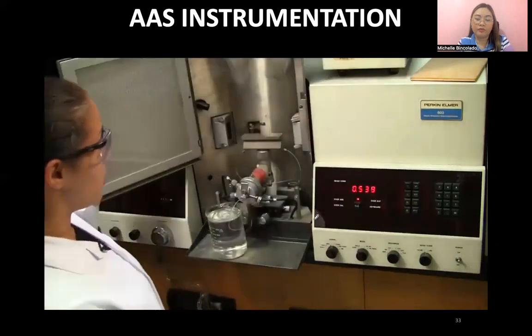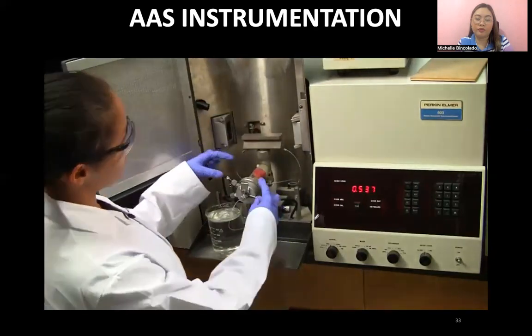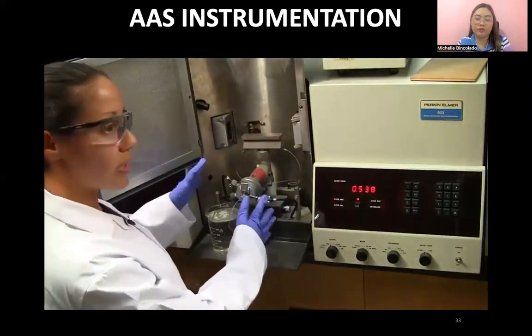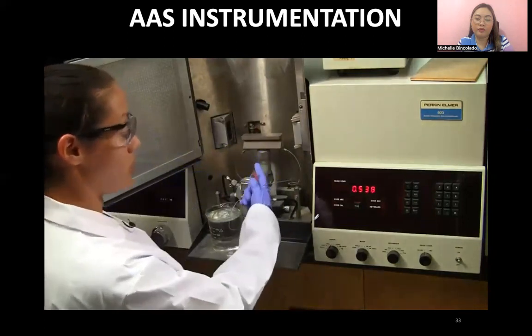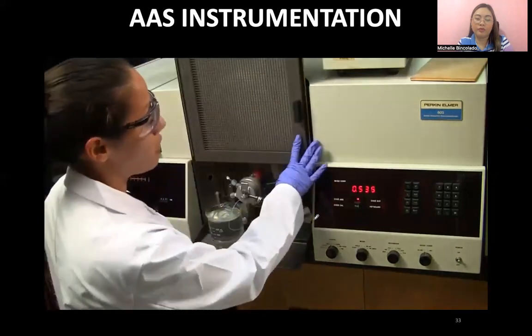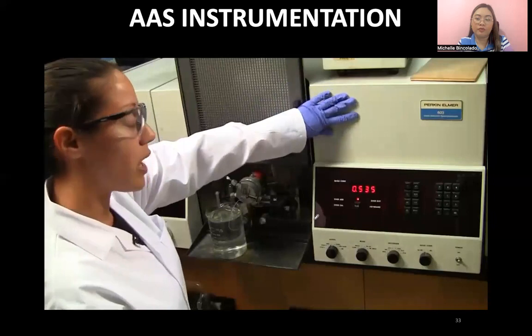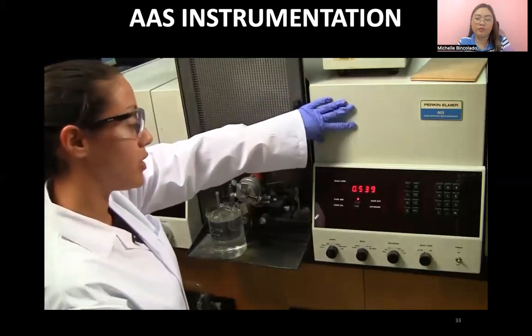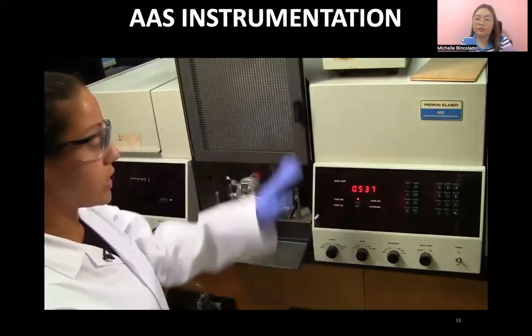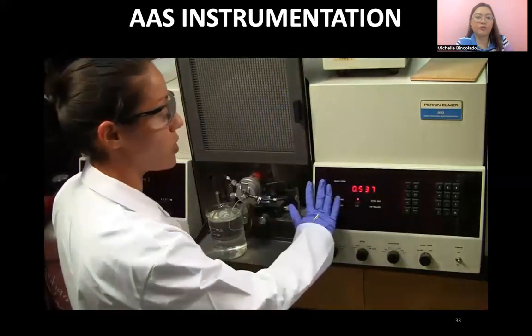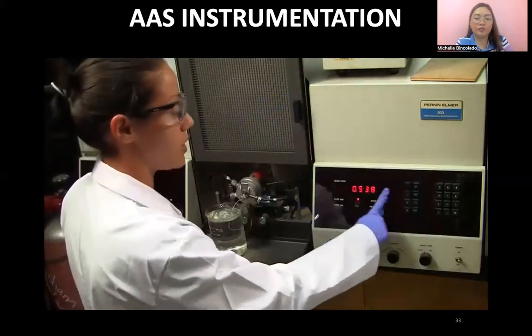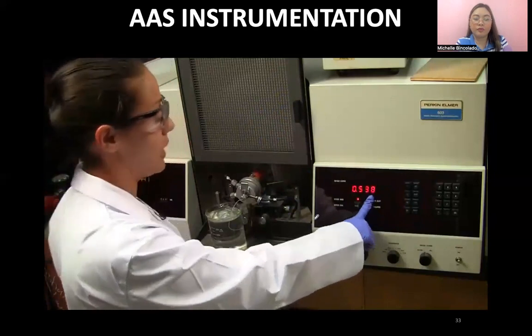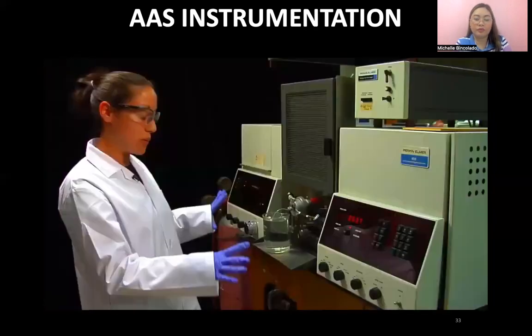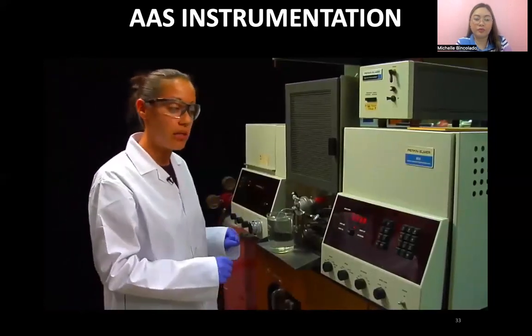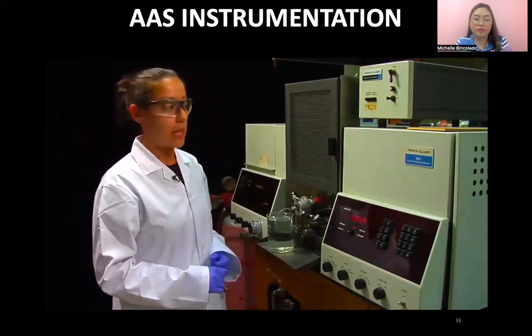Inside here, you have your burner. And this is where your premixer and aspirator are, where your sample is going to be sucked up to go into the flame. And in this part of the instrument, you have your monochromator, your detector, and your amplifier, just to give you a signal. So all those components allow you to give an absorbance reading here. Those are pretty much the main components. There's a lot of knobs and stuff, but again, you don't have to worry about that for sampling.